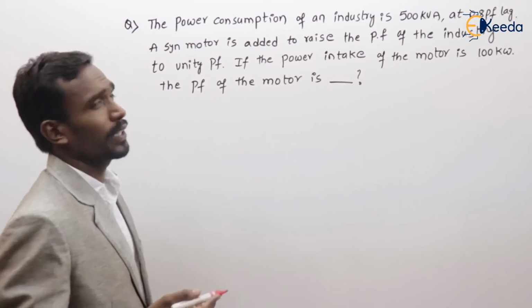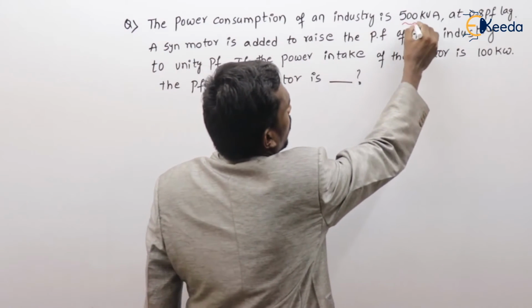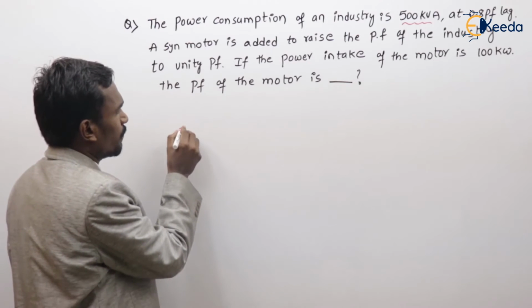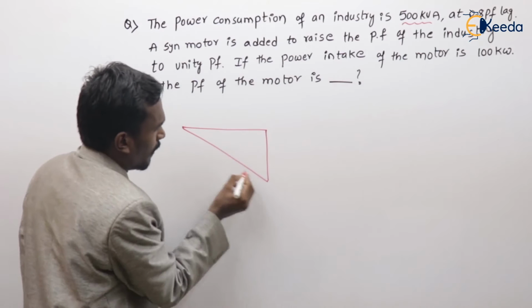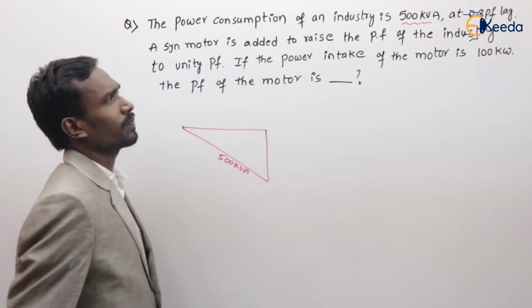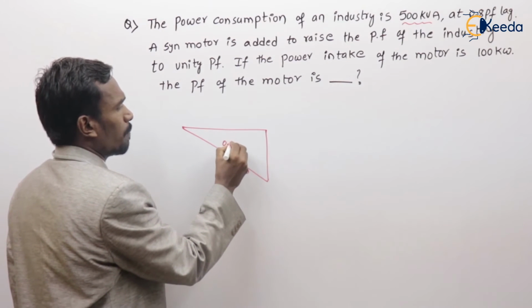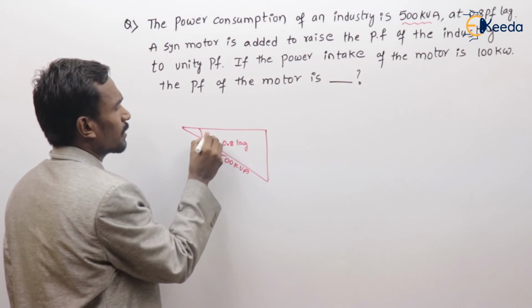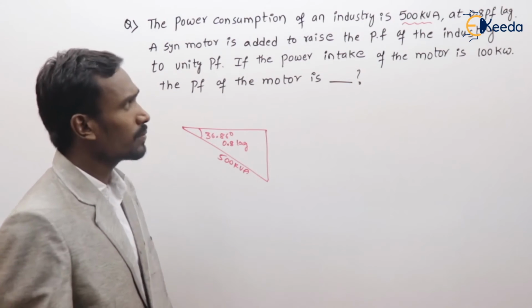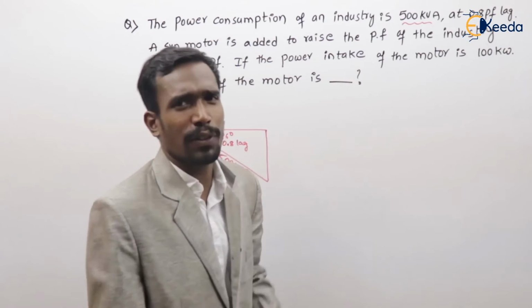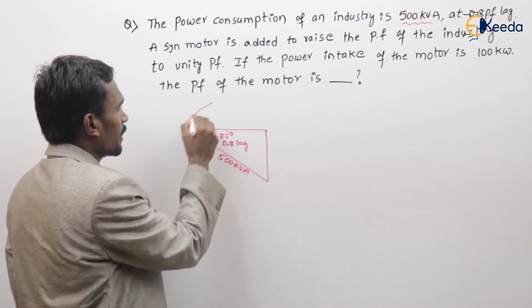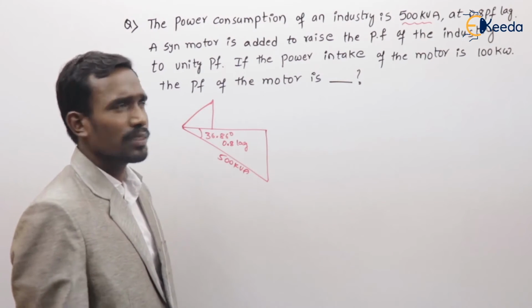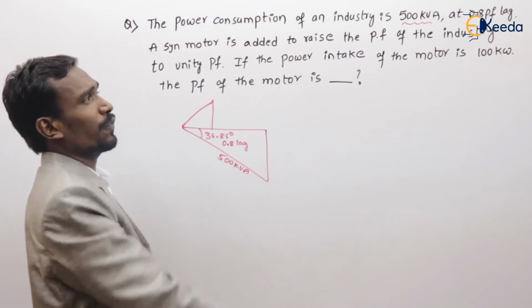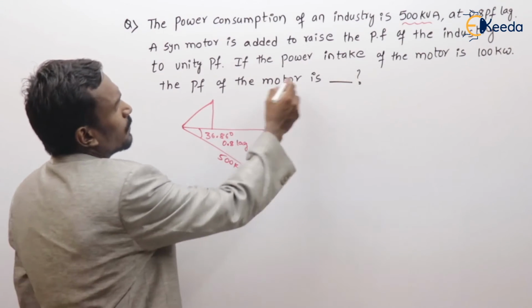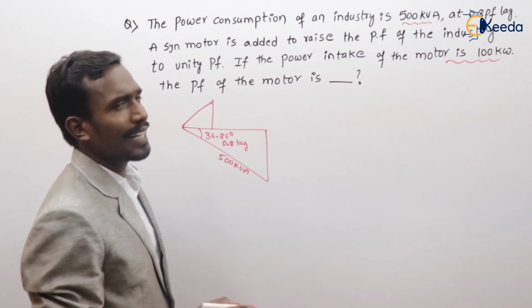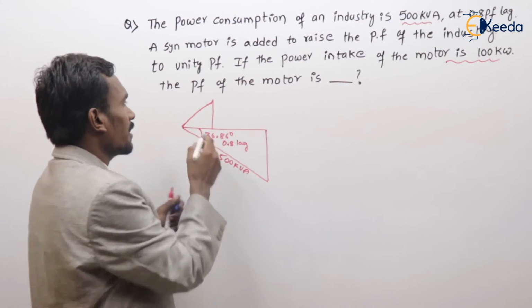Right, next question. See, this is a very important question. The power consumption of an industry is 500 kVA, its power factor 0.8 lagging, nothing but a 36.86 degrees angle. A synchronous motor is added to raise the power factor from 0.8 to unity. If the motor takes 100 kilowatts, the motor rating they gave is 100 kilowatts.